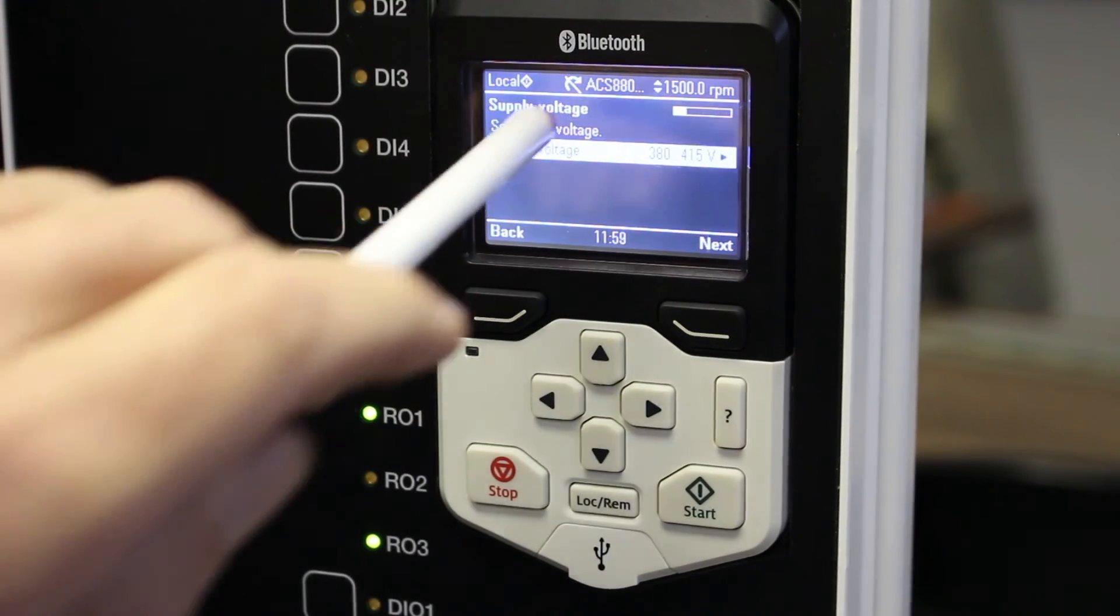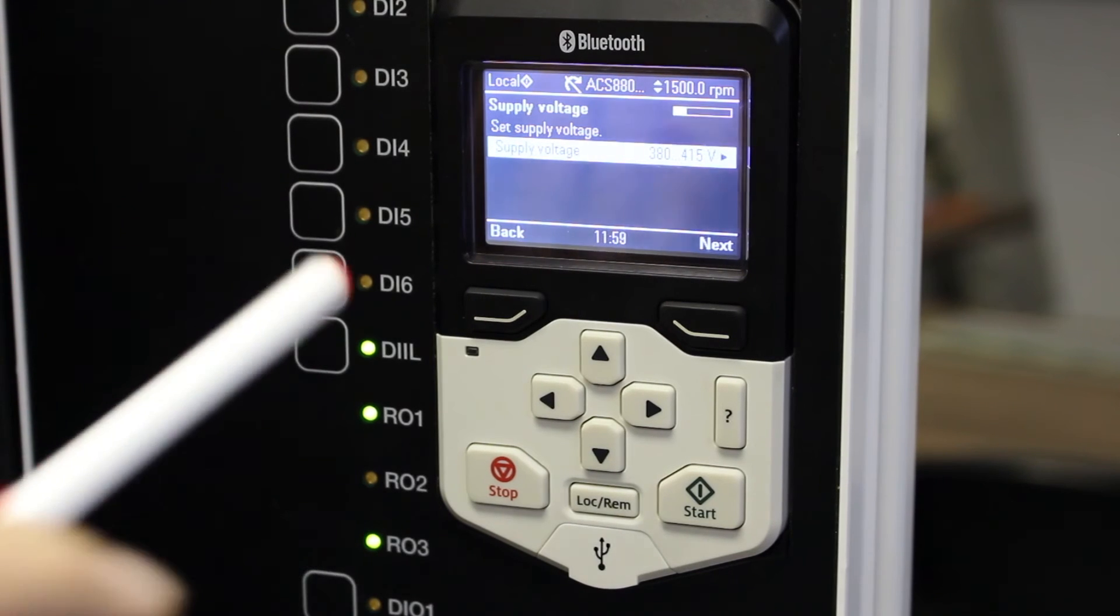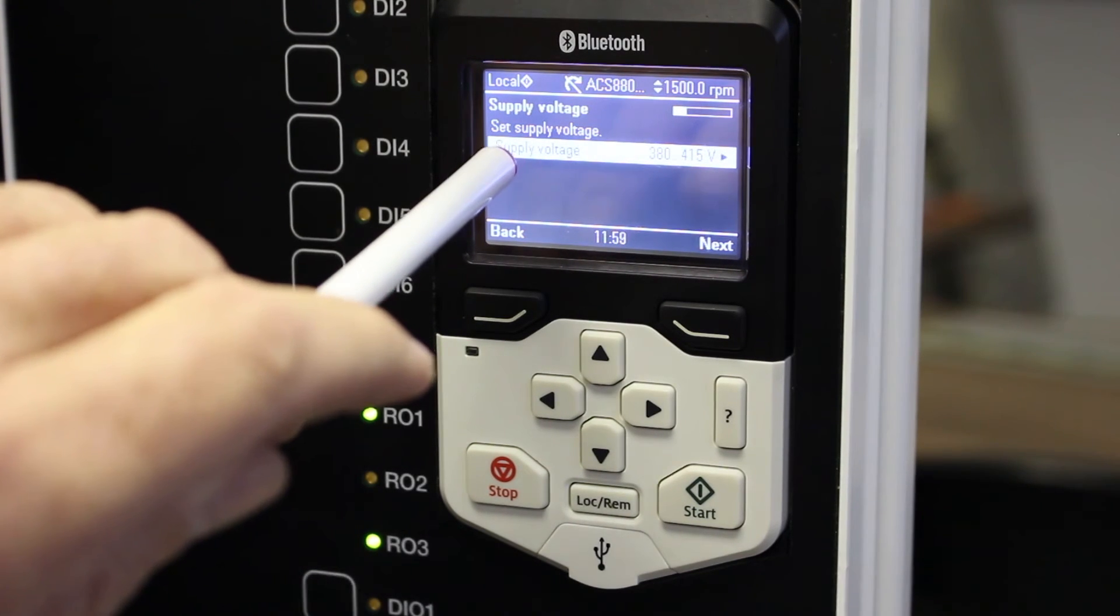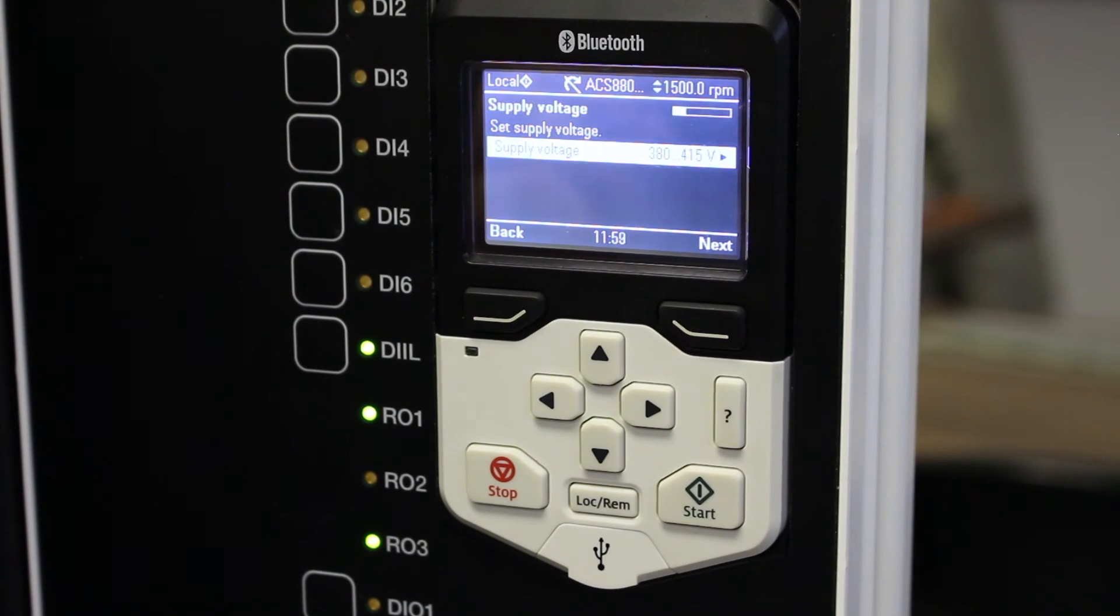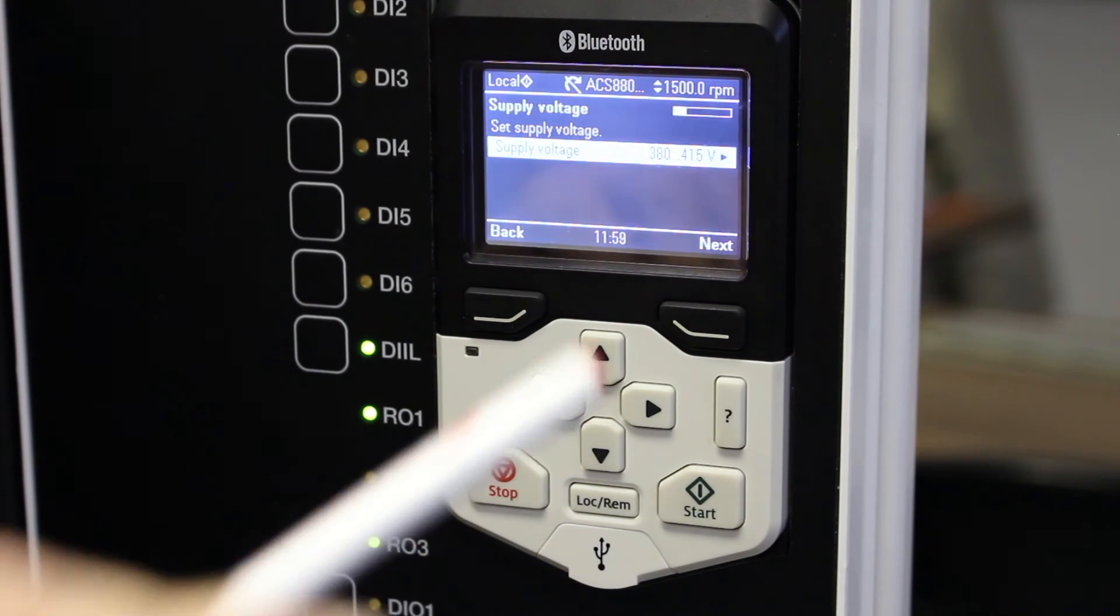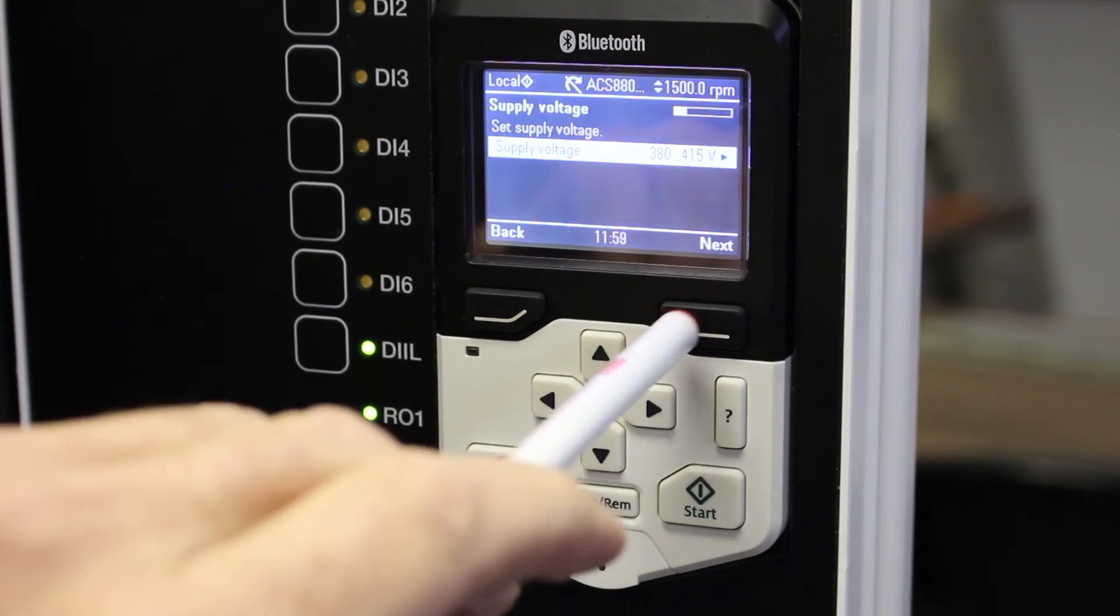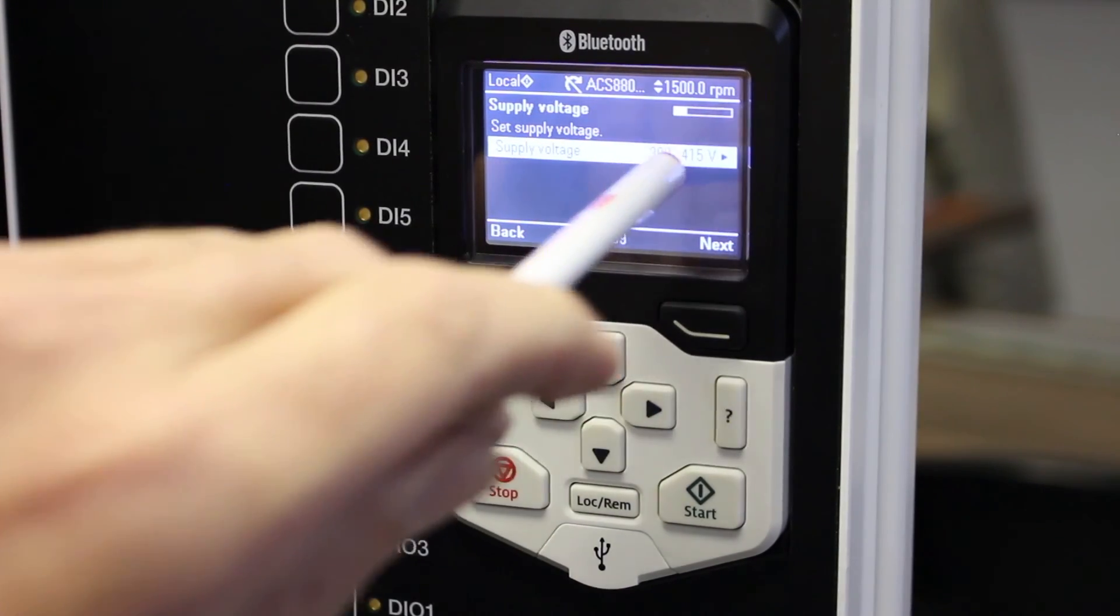Now supply voltage, this is becoming a little bit more technical. To change your supply voltage you need to know what the supply voltage for your drive is supposed to be. If you know the type code of your drive and you've got a dash three drive, it means you need 380 volt supply and that is what you will see over here. So I'm happy with the 380 volt supply and I go to next.